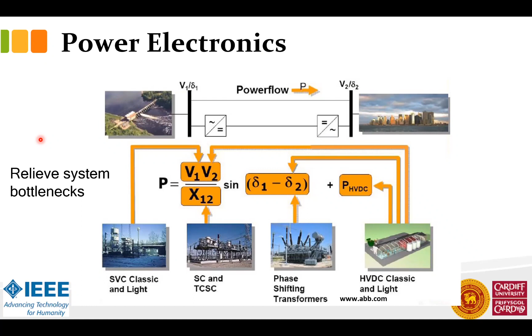This is a very simple example of smart grid. You've learned the power equation, V1 V2 over X sine delta, but you can manipulate any of these now. You can change the voltages using static compensators, the reactance using a series capacitor or a thyristor controlled series capacitor, the angle using a phase shifting transformer, and on top of that you can also add a DC line, which is independent of this equation.